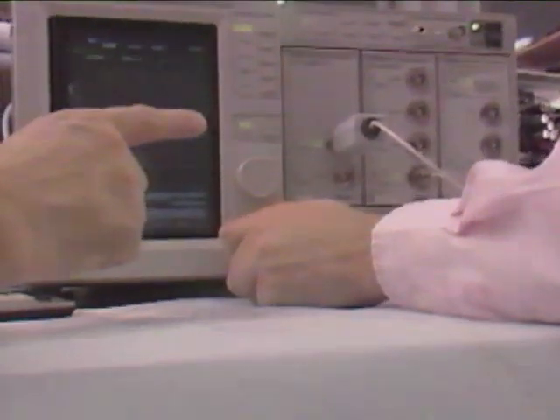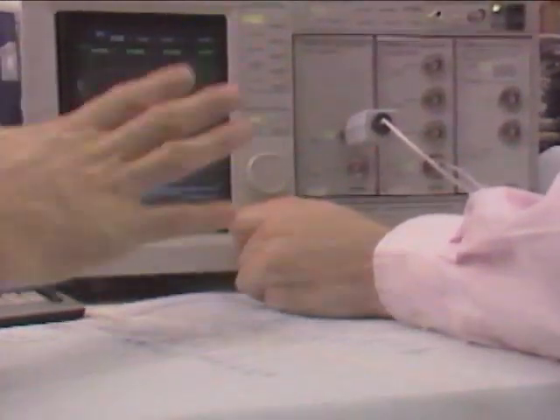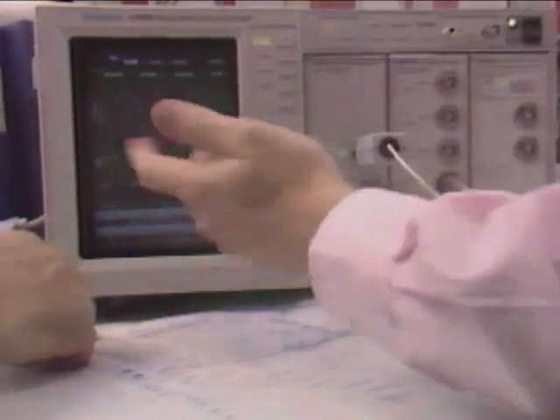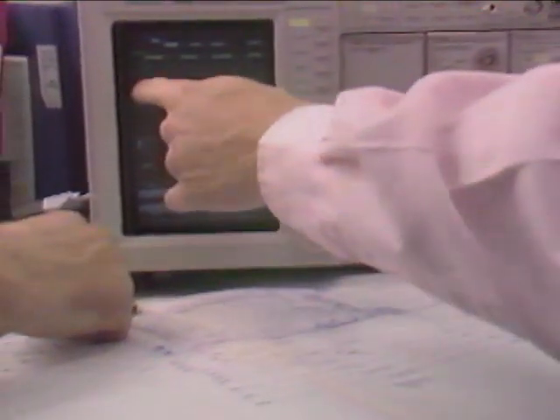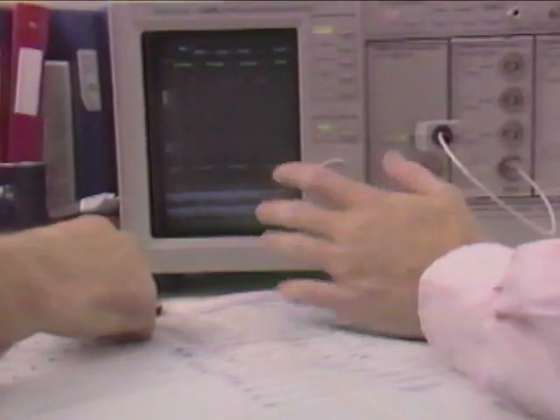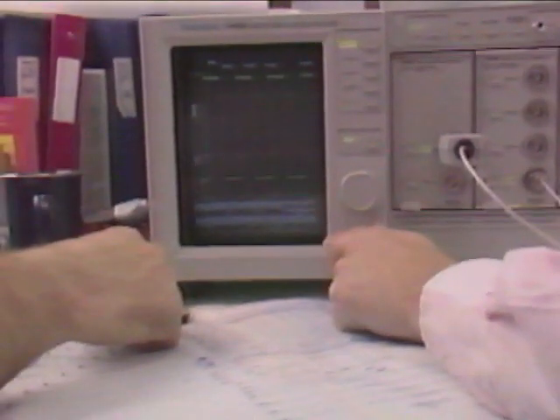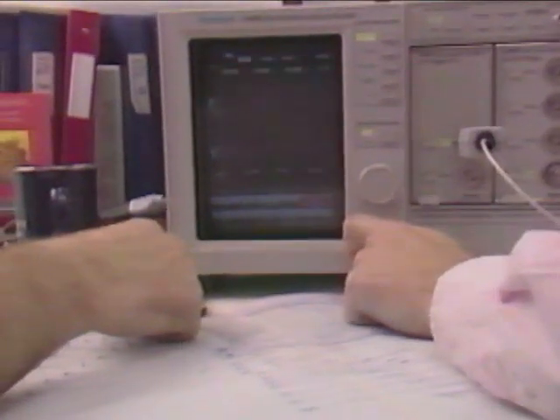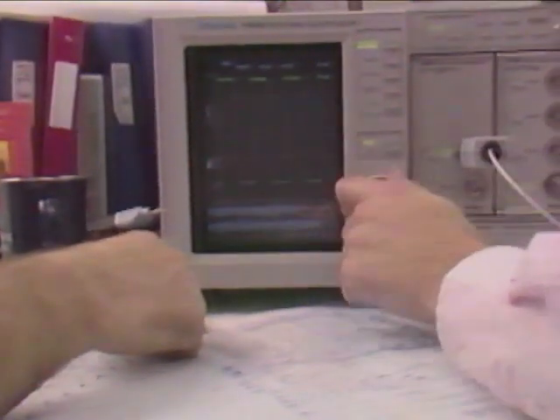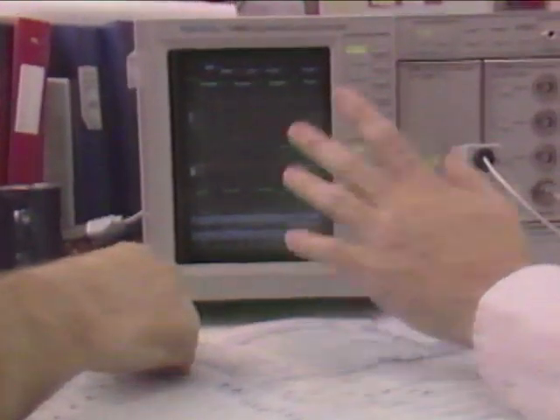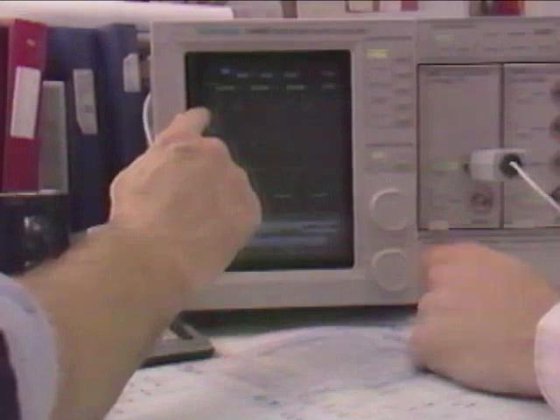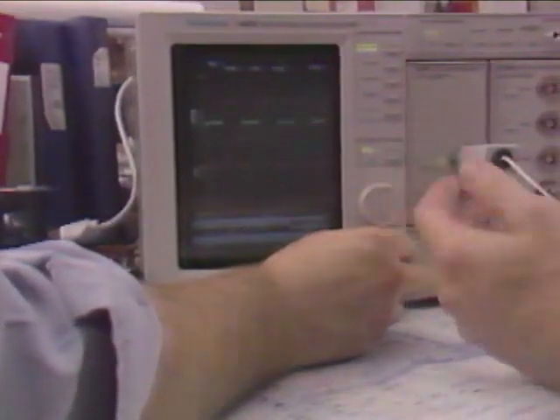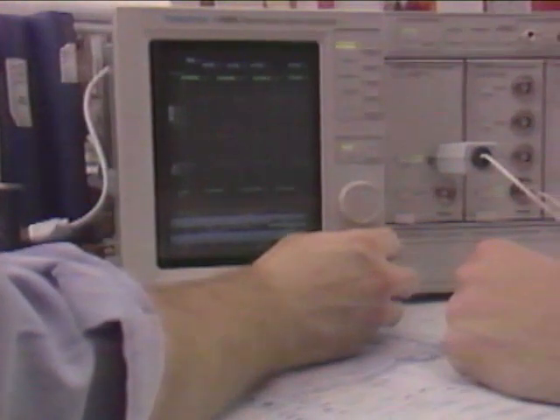Well, that's just for starters. Here, let me show you this. Hold it. What did you do? Are those knobs for vertical or horizontal or what? Well, vertical, horizontal, trigger functions. Just touch the appropriate icon over here. See, it illuminates when it's operative. And then the knobs are assigned to vertical size and offset. To horizontal time and position. And then to trigger level and trigger hold-off time. Now, you can also assign them to control zoom and pan, delay time, time per div, and then set them for coarse or fine adjustments without ever taking your eyes from the screen. Pretty slick.